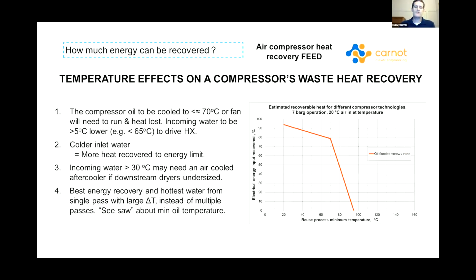So what are the temperature effects from recovering heat from an air compressor? Well, you need to maintain the temperature going back into your air end at that 60, 65, 70 degree mark. I'll just bring up a little spotlight. Can you all see that? So around about this point, you've got to maintain that temperature.